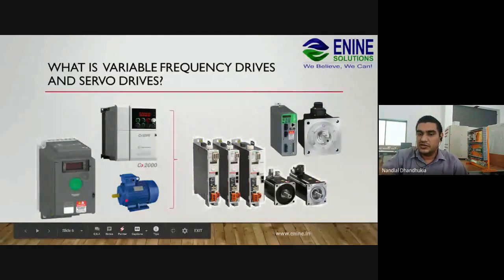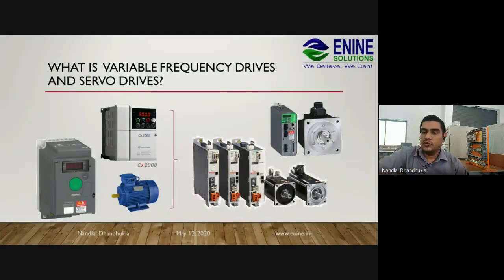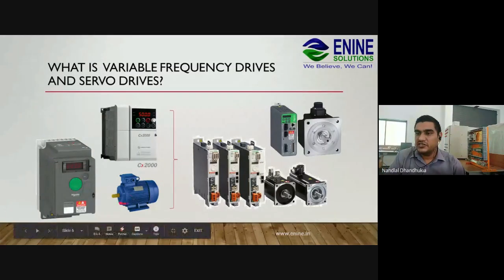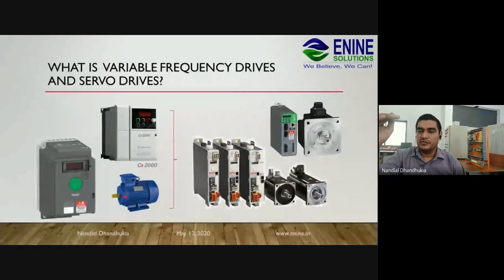So suppose there were 2 taps open, the pressure was 3 bar. Now suppose one more tap is opening, the pressure is dropping below 3 bar. So the PLC will increase the speed of the drive, and that eventually increases the speed of the motor, and again the pressure will be built up at 3 bar. So in a pipeline you will get constant pressure throughout the system. That is called a hydro-pneumatic pressure booster system.